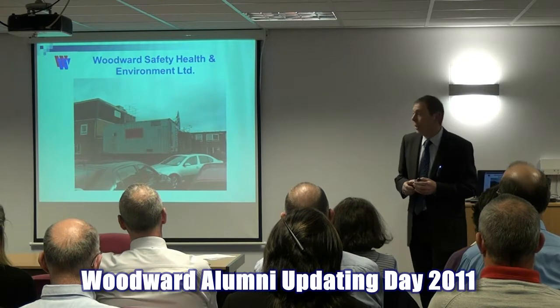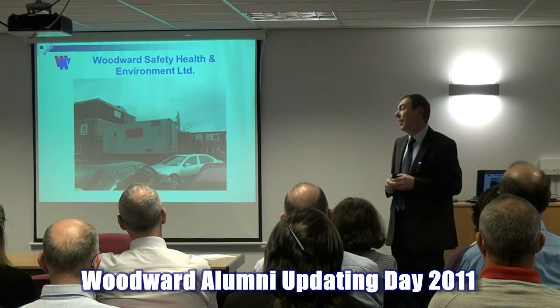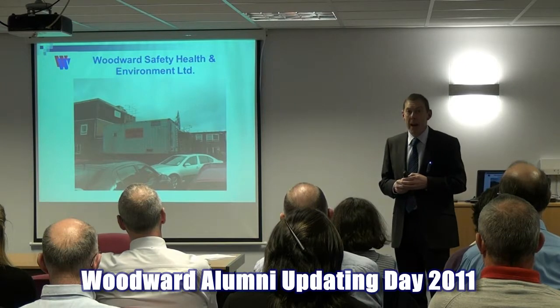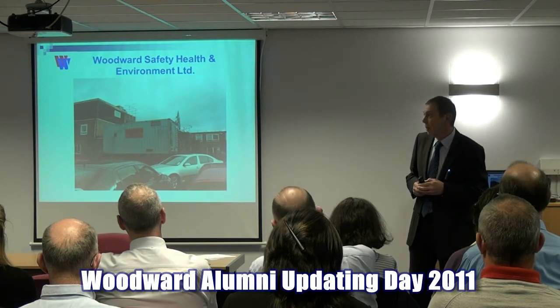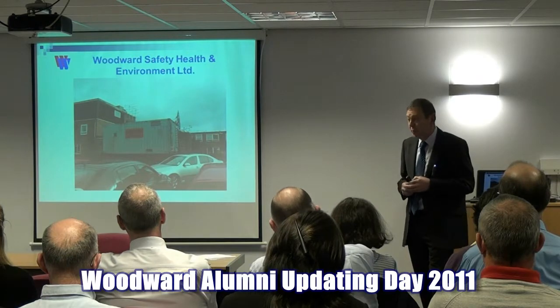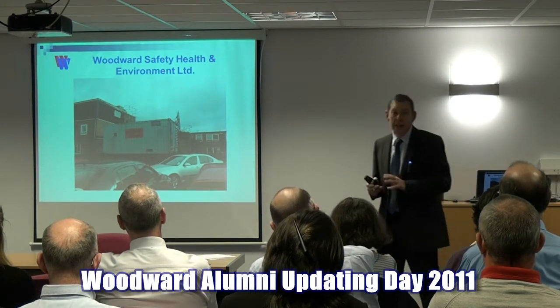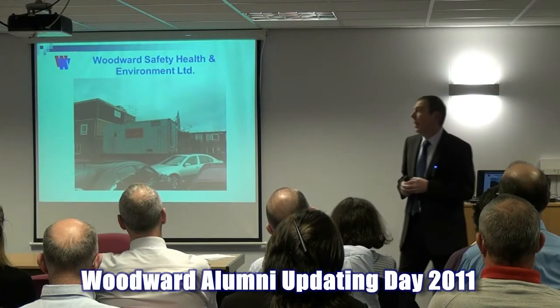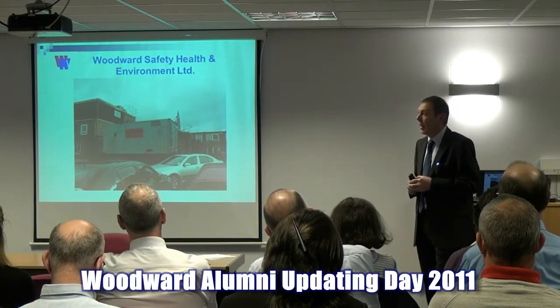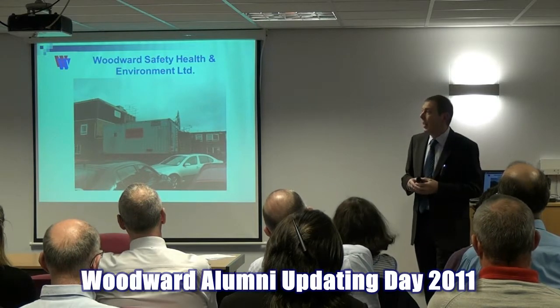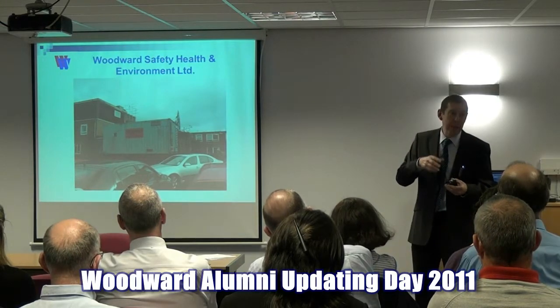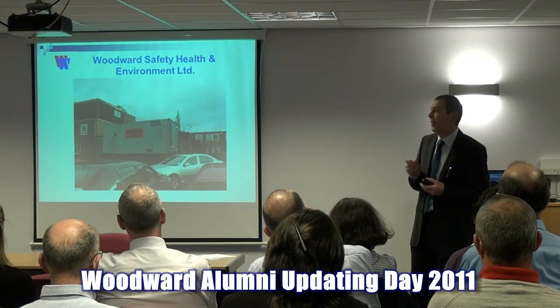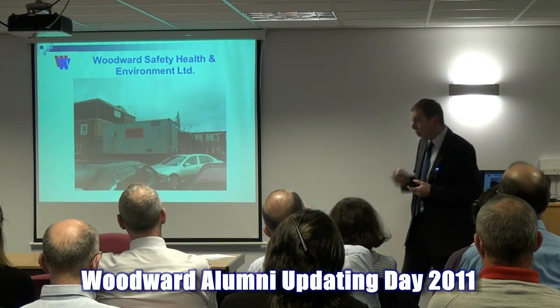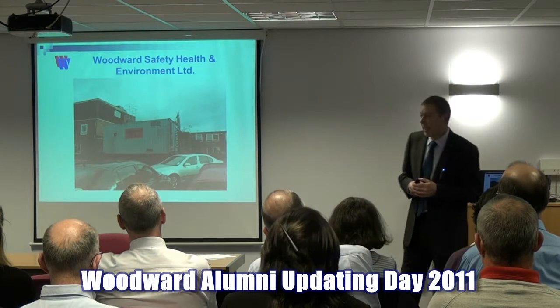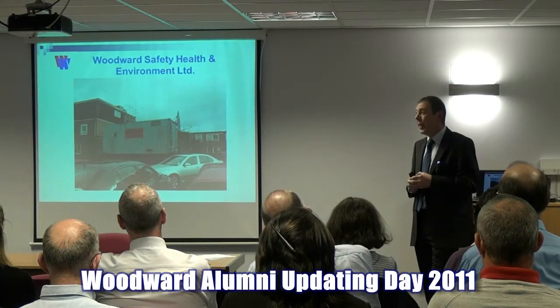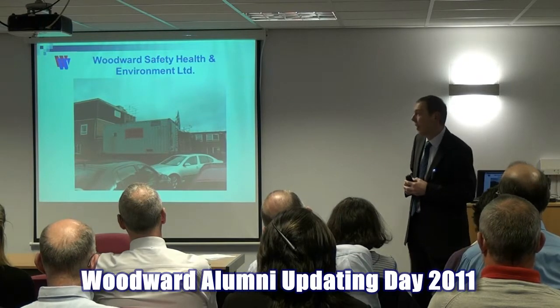We came to the conclusion the only way to do it was to get a generator of the size that would satisfy the demand of the building, which turned out to be 500 kVA. That's a pretty big generator. To give you some idea, anybody been at the fairground and seen a standard fairground ride? If it's a small to medium generator on the back of the truck that the fairground ride comes on, that's about 30 to 50 kVA. If they're towing the generator, there's a good chance it's going to be about 50 to 100 kVA. We needed 500 kVA. It's a big generator.